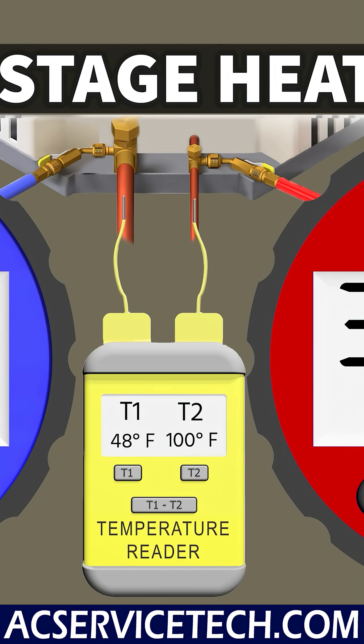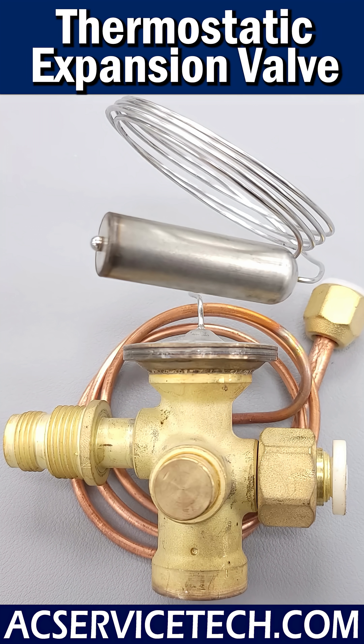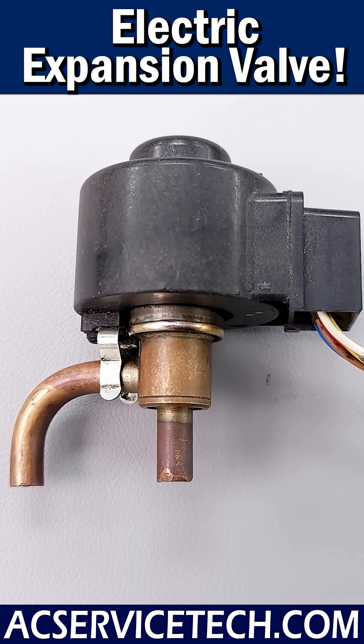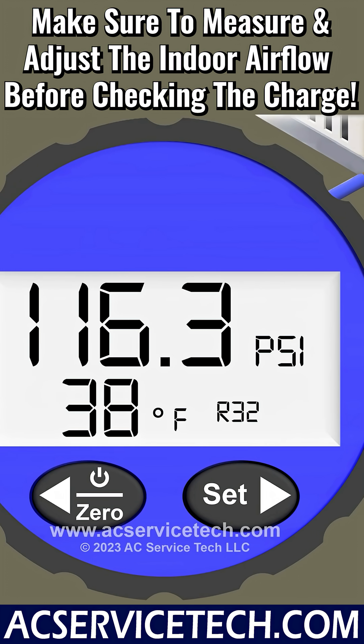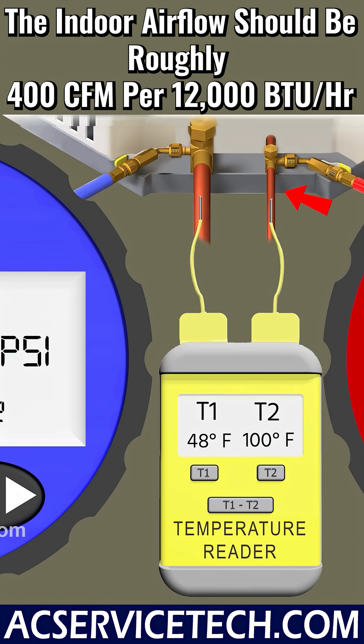We're going over how to check the refrigerant charge level on a single-stage air conditioning or heat pump system equipped with R32. You want to check to make sure that you have a thermostatic expansion valve or an EEV at the indoor coil. We're going to be measuring the subcooling method, which is measured on the small liquid line during air conditioning mode.